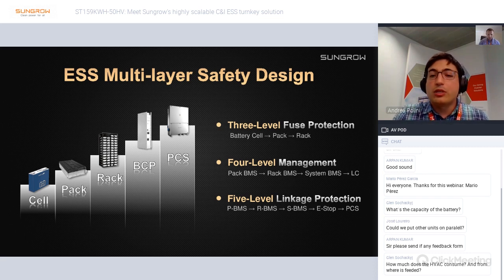In addition to this, the ESS itself is designed for redundancy on the whole safety chain. We have, first of all, 3 levels of redundancy on the electrical protection, with the fuses on different levels: the battery cell, the battery pack, and the battery rack. In addition to the protection devices for the DC circuit that you can find in the battery connection panel.